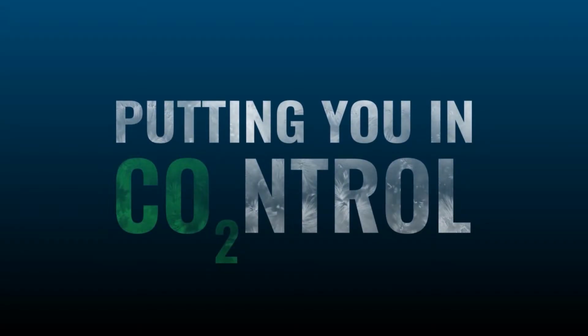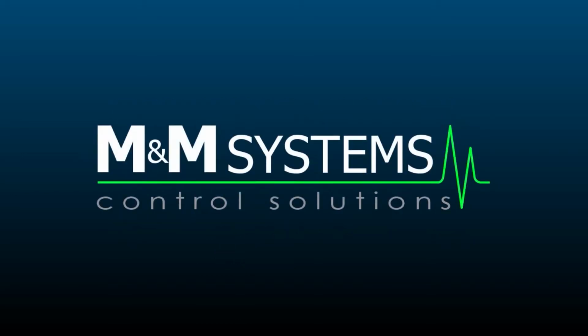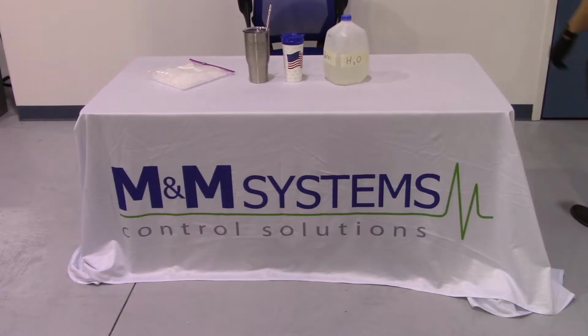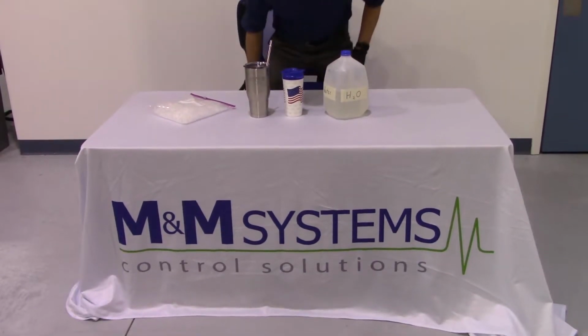Today, we are exploring how to properly calibrate a temperature sensor using the melting point of ice as a reference for 32 degrees Fahrenheit. When properly prepared, this solution is accurate enough to ensure valid readings of the sensor down to the 10th of 1 degree.